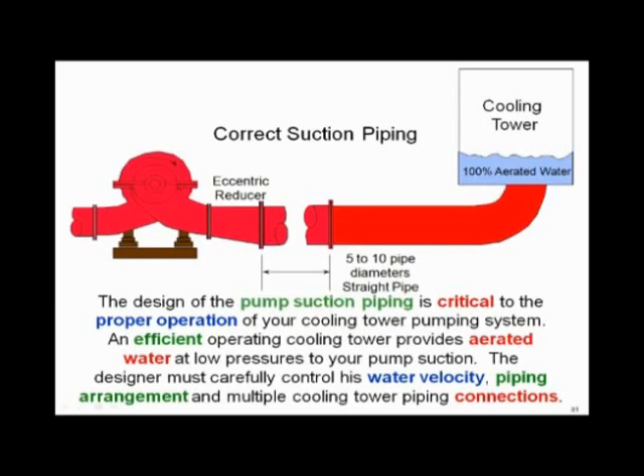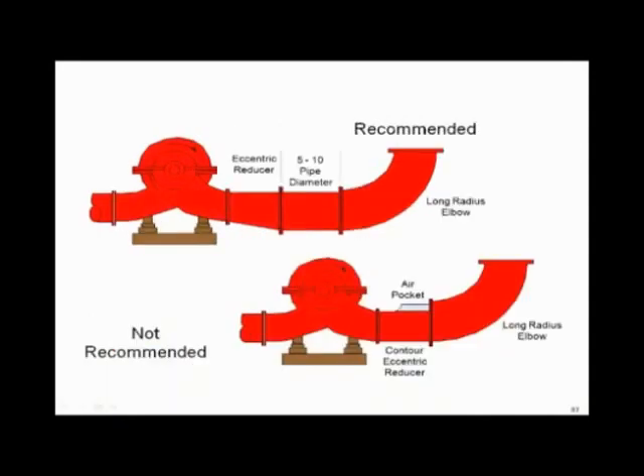A cooling tower aerates water for a living. It will reduce the pressure, that air is going to come out. So in piping, we like five to ten pipe diameters straight pipe. The little bottom picture shows that air pocket. That's bad. You don't need part of that. That's where air is going to collect. You get a big bubble of air coming out into the pump.